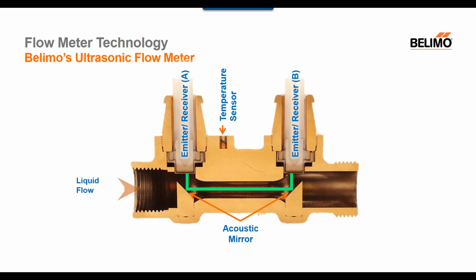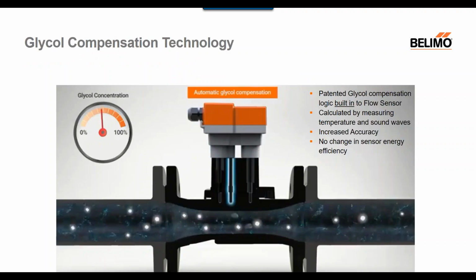Then an ultrasonic signal is transmitted from transmitter A to receiver B, and then vice versa from transmitter B to receiver A. Using the patented ultrasonic flow technology, you can compensate for high density glycol solutions, which is used in the majority of applications within the Americas, and to accurately measure the true flow of the system versus having to manually measure and manually enter the glycol percentage into the device or directly into the BMS, thus allowing you to obtain true, trusted flow measurement.